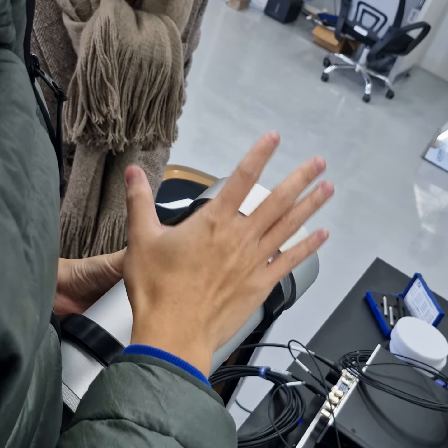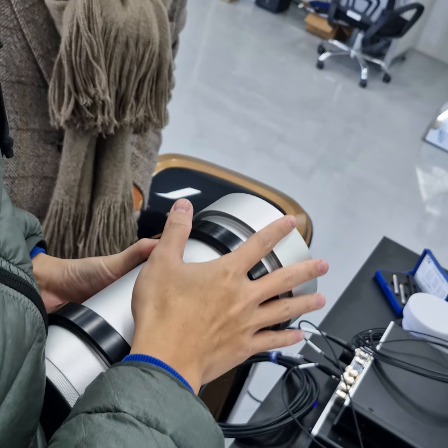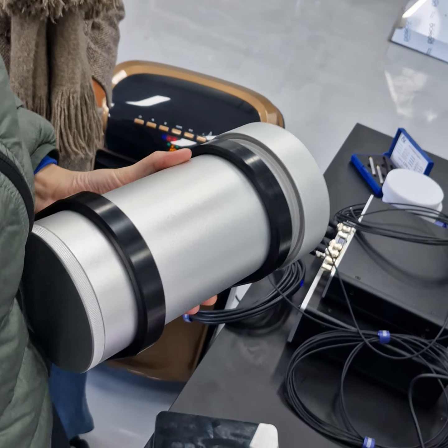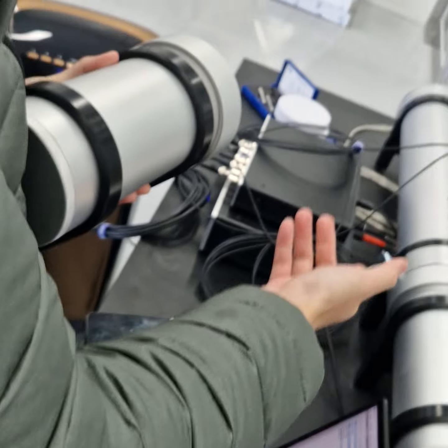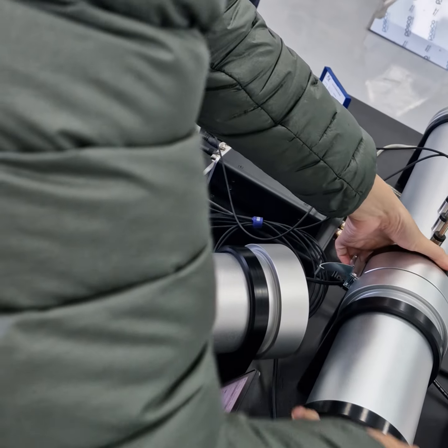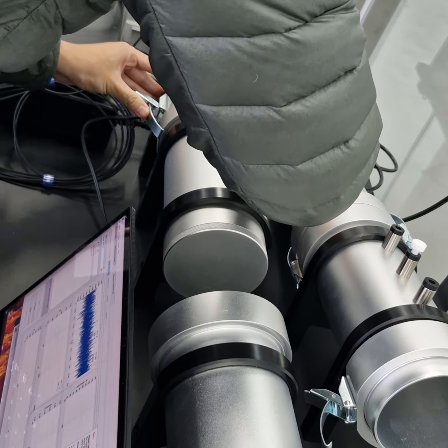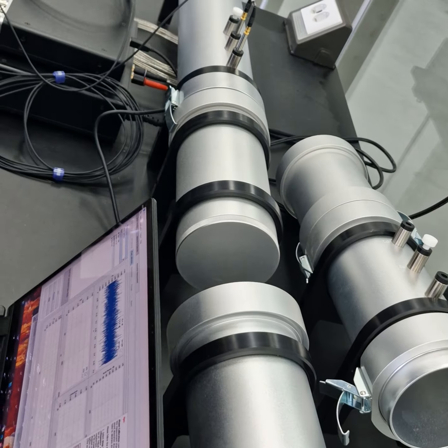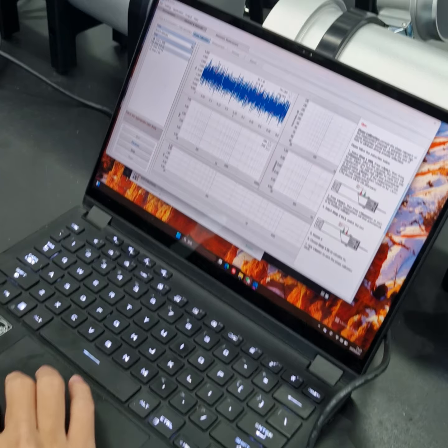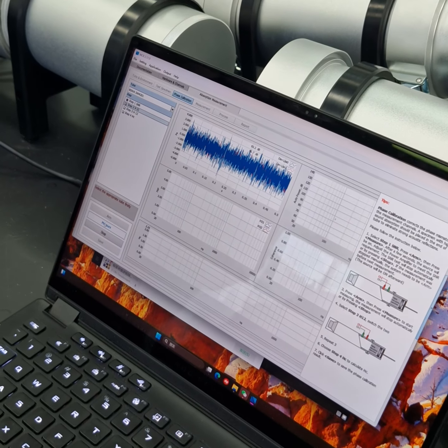This is the highly absorptive material tube. So when you're doing the phase calibration, you can just replace this tube with this. Okay, so we do the H12 test. We click measure.